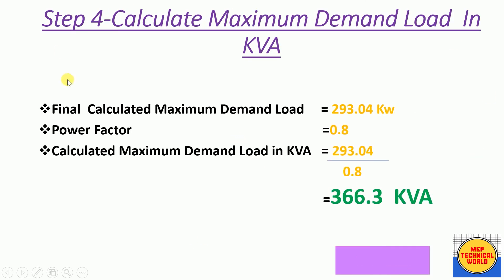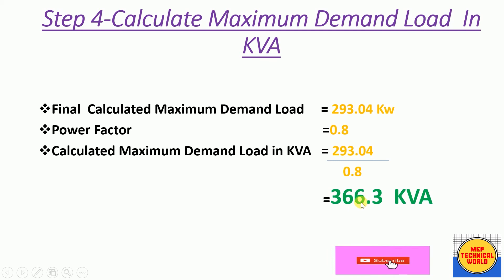In Step 4 we convert the maximum demand load from kilowatts (active power) to kVA (apparent power). The calculated maximum demand load is 293.04 kW. To convert to kVA we use a power factor of 0.8: maximum demand load in kVA = 293.04 / 0.8 = 366.3 kVA.